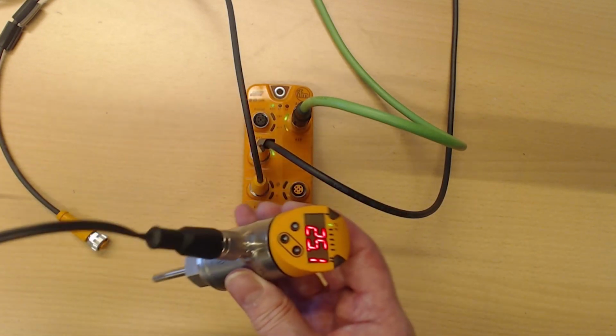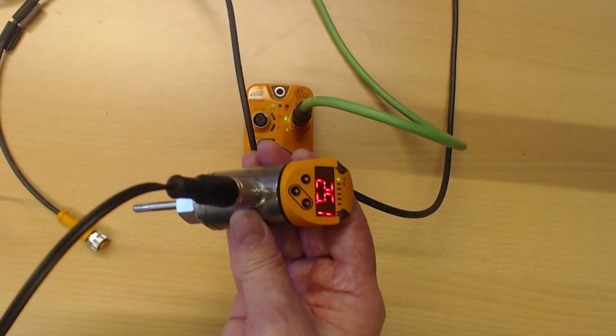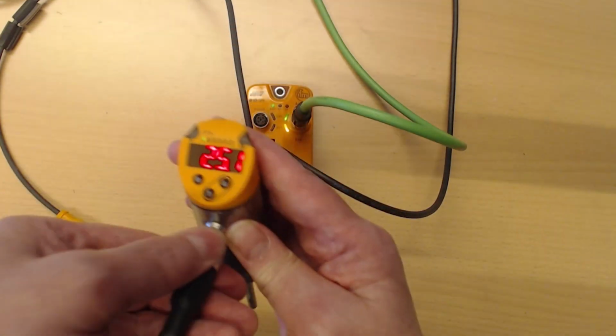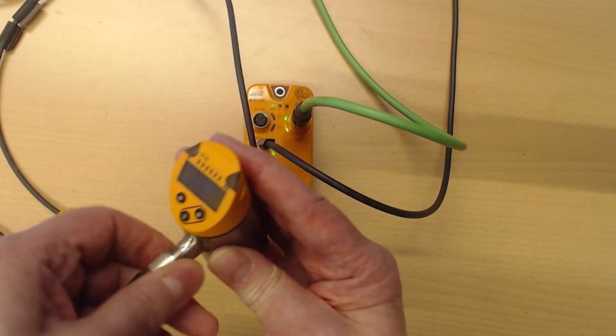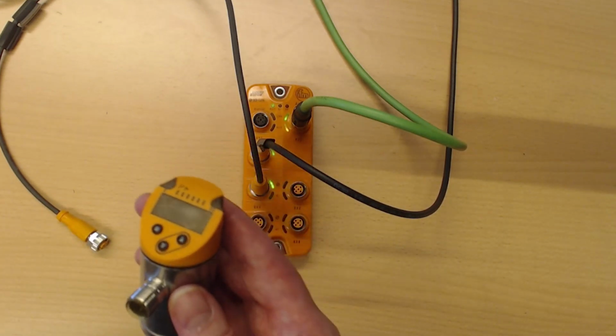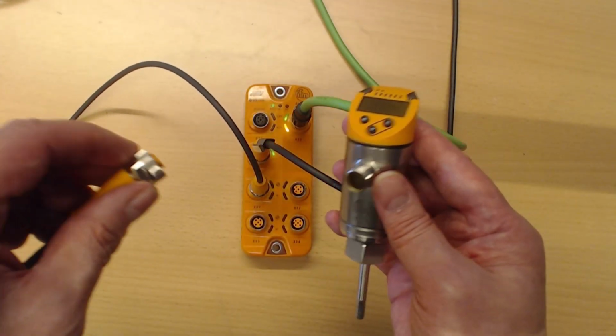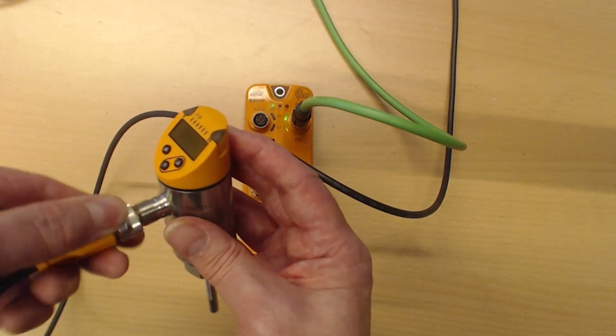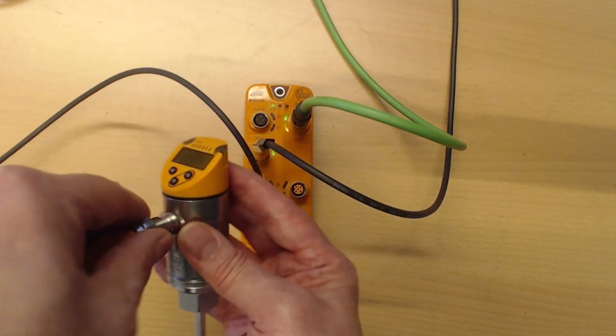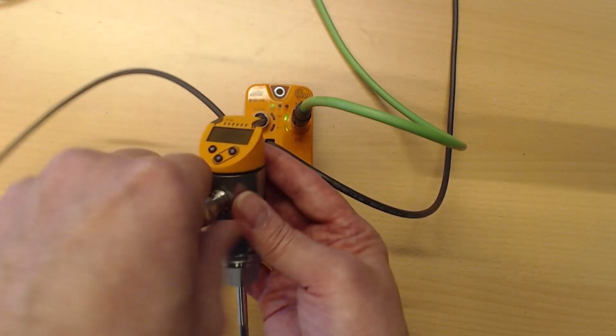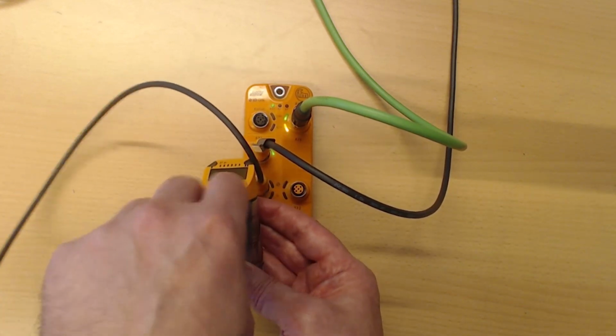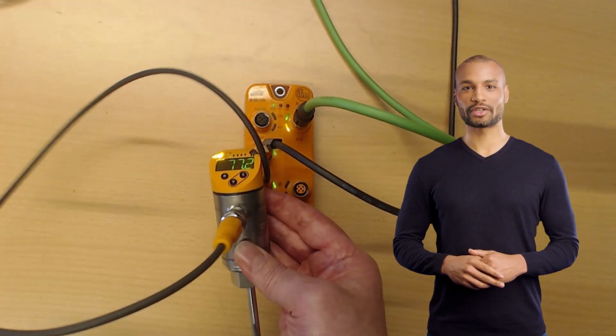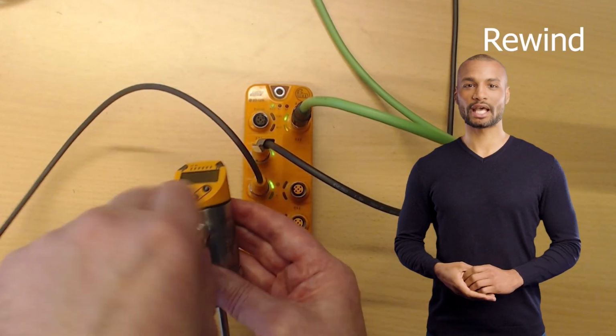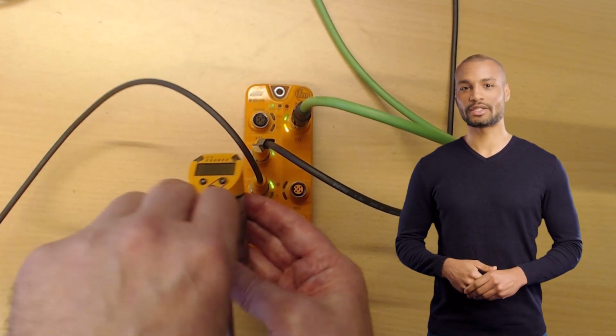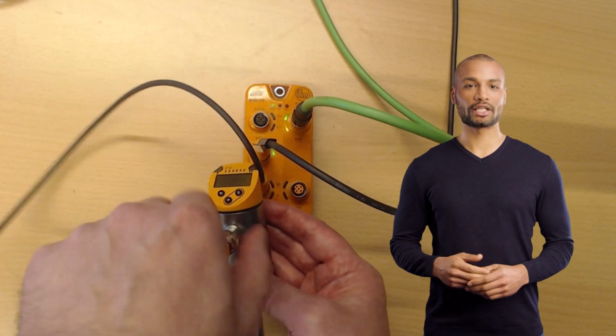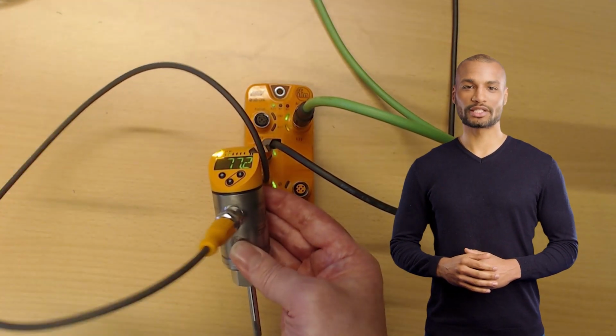Now we reconnect this sensor to the IO link port of the master that we have configured and see what happens. The master recognizes that it is a factory configured device and overwrites the stored parameter set. When the transfer is successful, the sensor display changes to green and the unit is degrees Fahrenheit. The new temperature sensor is now parameterized in the same way as the previous unit. It is important to note that the restore function only works if the connected sensor has the factory settings. Otherwise, the current parameter settings of the connected sensor will be stored in the port, which corresponds to the backup function.